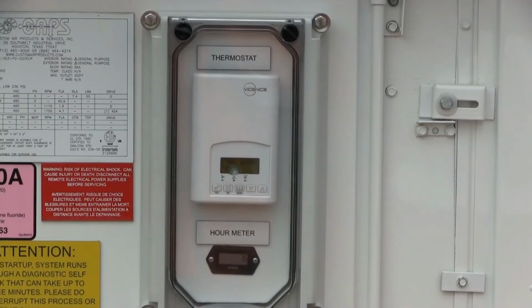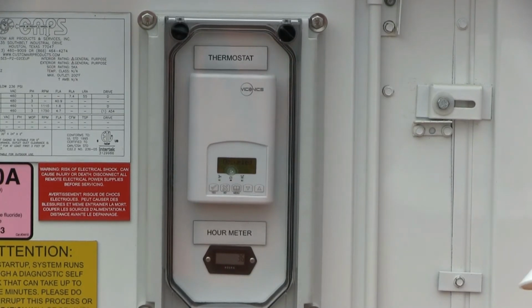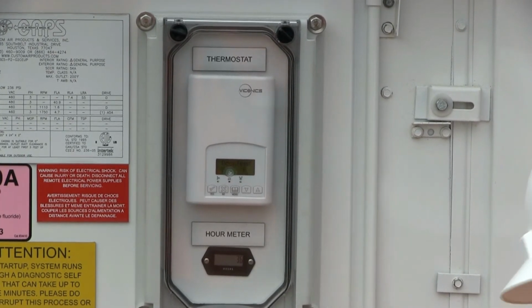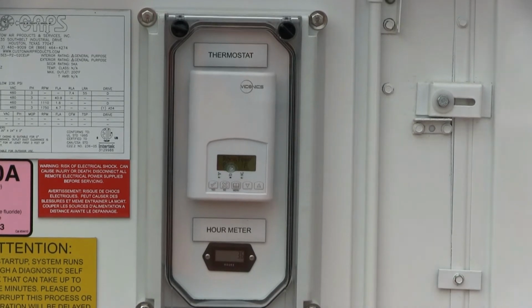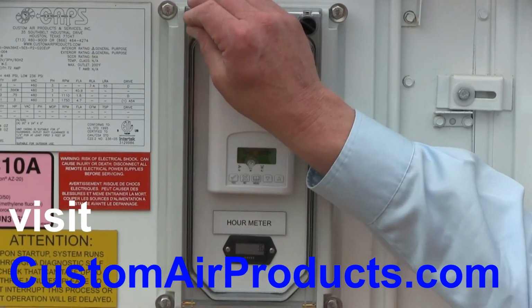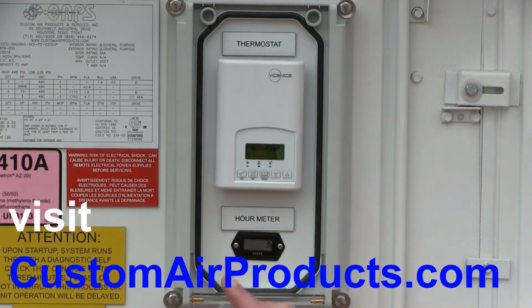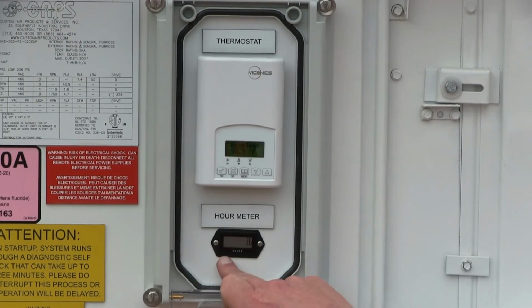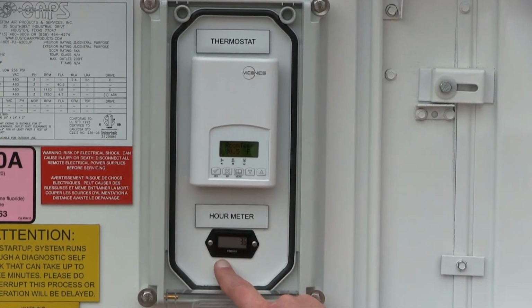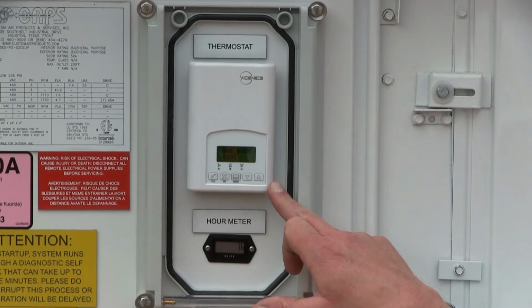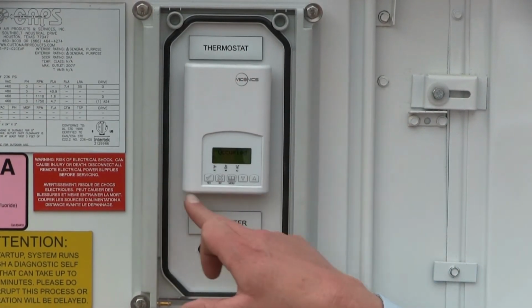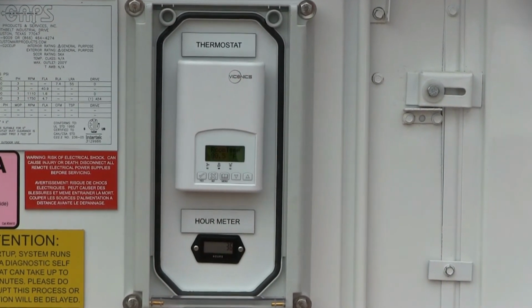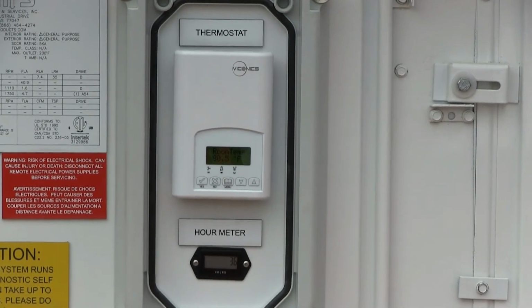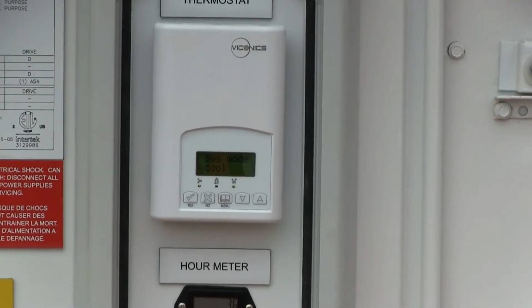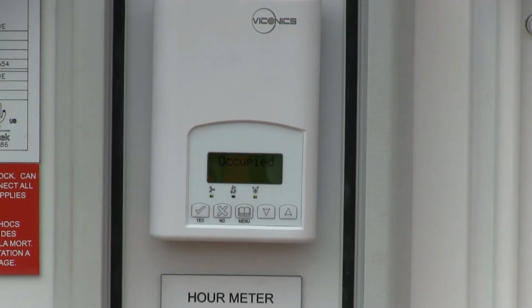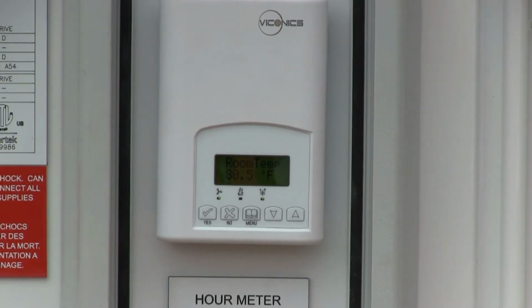thermostat. Now that we've completed all of our high voltage power connections and our ductwork, we no longer need our safety hot gloves here. Simply going to open up the protective cover over the thermostat. It goes down. Notice we have an hour meter in here that counts how many hours the machine's been in operation. This is a digital thermostat that controls all the functions of both the heating and cooling. The thermostat can be set for 4 different modes. It can be set for off, cooling, heating, or automatic changeover.